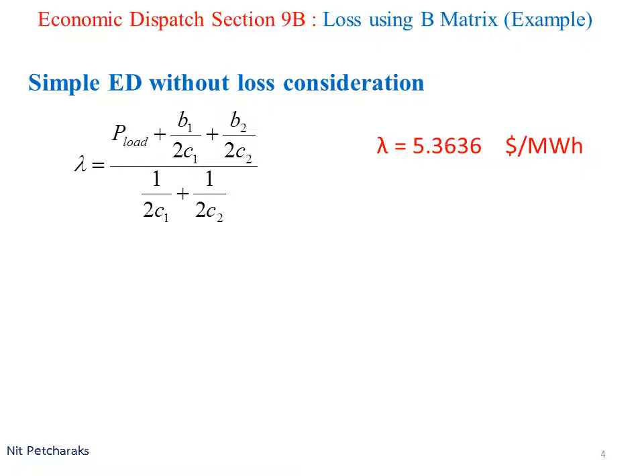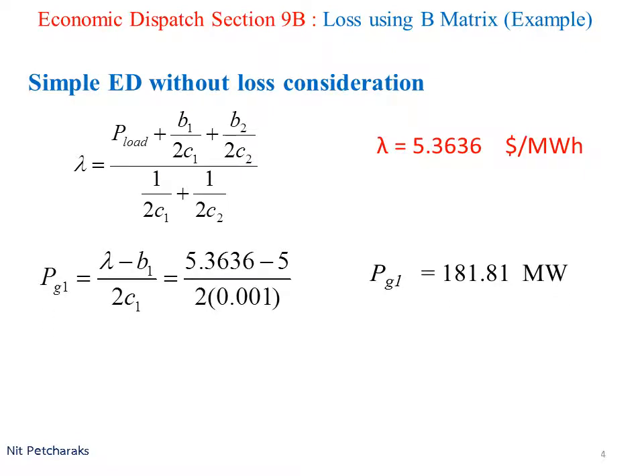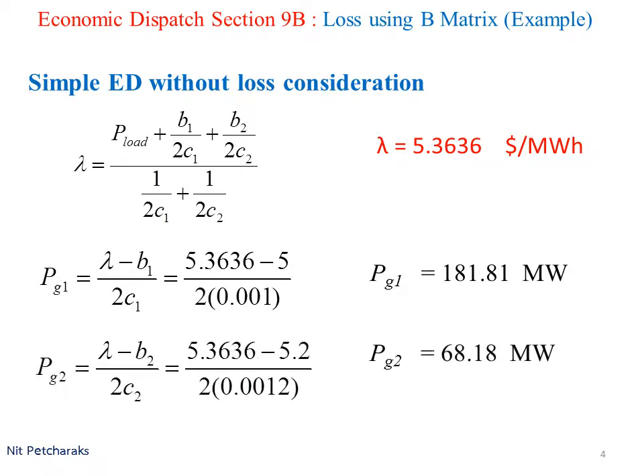We've got the value of incremental cost, approximately $5.4 per megawatt hour. Then we calculate PG1 and PG2. PG1 is approximately 182 megawatt, whereas PG2 is 68 megawatt. P-load is 250 megawatt.